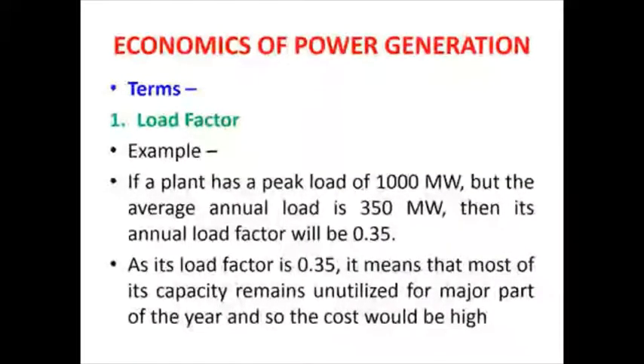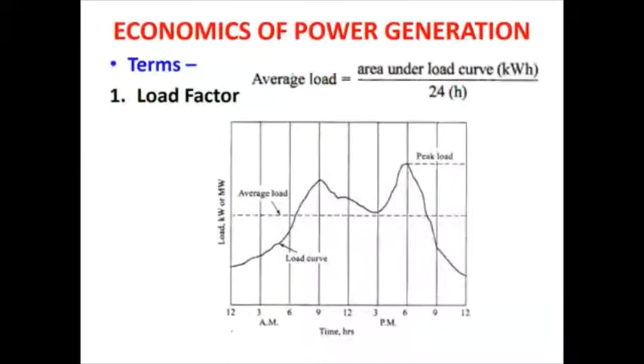In one example which we mentioned earlier, the load factor was 0.9, which is a higher load factor. Therefore the cost of electrical generation was less. But in this case, if the load factor is 0.35, then the cost of electrical energy generation will be higher. Now the example of a load factor. You can see two dotted lines on this chart. One is the average load, meaning the average of all the demands, and the other is the peak load, which is the maximum load.